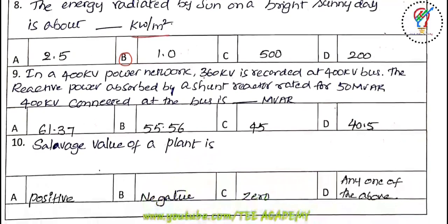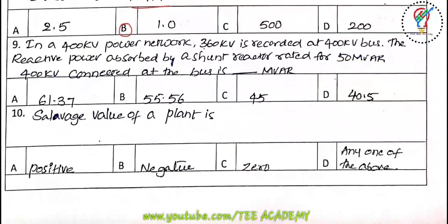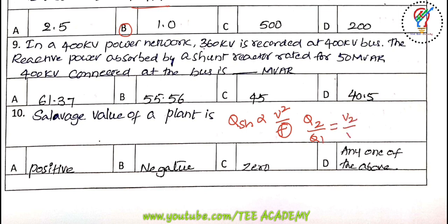Ninth question — a numerical problem: in a 400 kV power network, 360 kV is recorded at the 400 kV bus. The reactive power absorbed by a shunt reactor rated for 50 MVAr connected at the bus is how many MVAr? The hint is that Q for a shunt reactor is proportional to V²/X, where X is constant. So Q2/Q1 = (V2/V1)². Applying this relationship, the answer is option D: 40.5 MVAr.